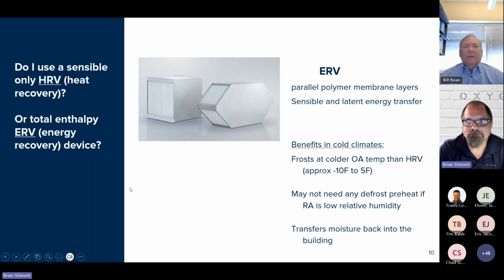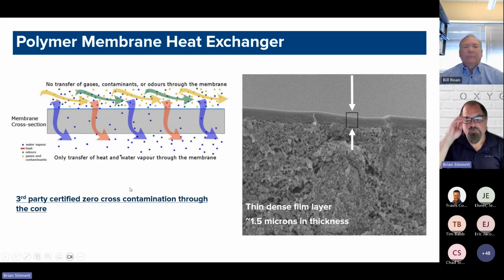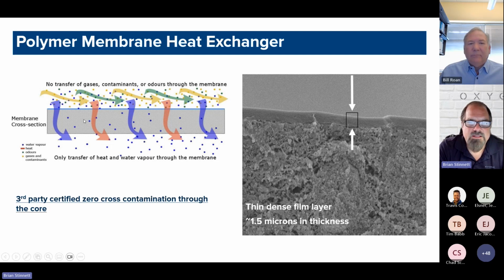Other things to think about. So if we look for a minute at that polymer membrane that I mentioned, it's a thin plastic membrane. It has tiny pores in it that are just big enough for a water molecule to move through. So it transfers temperature, but it also transfers moisture from the more humid airstream to the more dry airstream. And that's what allows it to transfer that moisture back and forth across that barrier. Still no cross-contamination in the heat exchanger. It is totally separated. Exhaust air is totally separated from the incoming outside air.